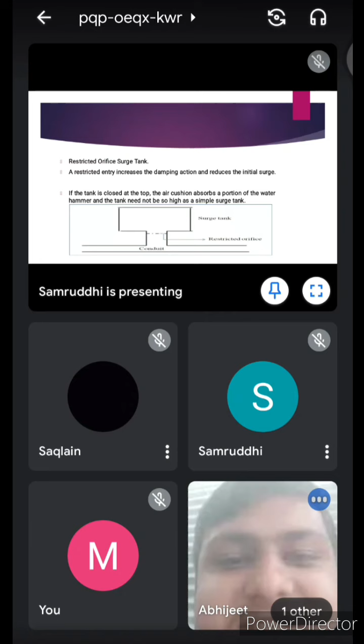Second one is a restricted orifice surge tank. A restricted entry increases the damping action and reduces the initial surge. If the tank is closed at the top, the air cushion absorbs a portion of the water hammer and the tank need not be as high as a simple surge tank. A restricted orifice constitutes an orifice between the pipeline and the surge tank. To reduce the water hammer effect, the diameter of the orifice should be well designed for full rejection of load by the turbine.